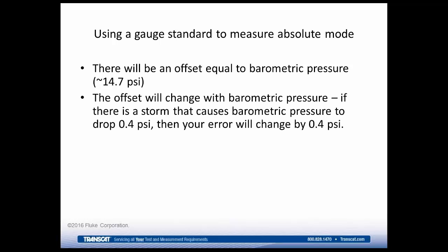And the amount of that offset will change with barometric pressure. So when you first turn them on, they may be reading 0 and 14.7 psi. As you sit there, the barometric pressure in your room changes. One of them will continue reading 0, and the other will read, say, 14.3 psi. So you've got an error that's more or less a continuous offset, but the amount of that offset will change with barometric conditions.